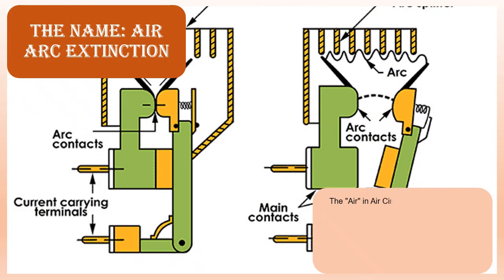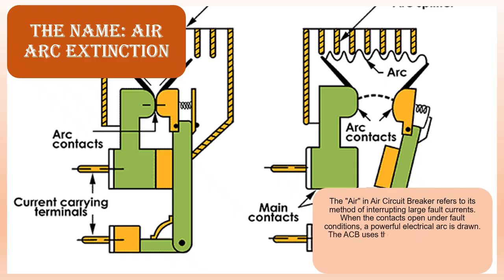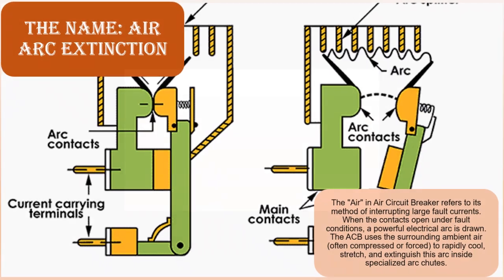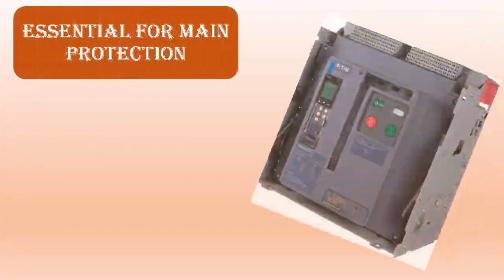The name, air arc extinction. The air in air circuit breaker refers to its method of interrupting large fault currents. When the contacts open under fault conditions, a powerful electrical arc is drawn. The ACB uses the surrounding ambient air, often compressed or forced, to rapidly cool, stretch, and extinguish this arc inside specialized arc chutes.